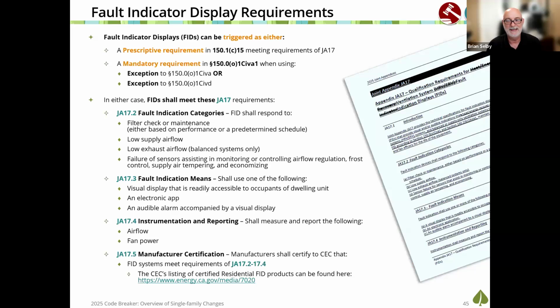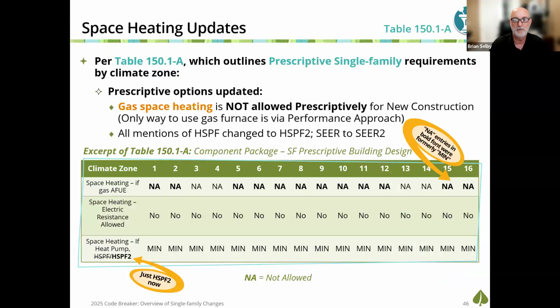There are some really in-depth requirements for this fault indicator display to qualify under the reference joint appendices chapter 17. Not going to get into these in any depth here, but just understand that minimum requirements have been set by the Energy Commission for these devices to ensure that they're indicating the correct issues, like checking the filter to make sure that it's clean, and making sure that air is flowing through it. So we want to make sure that those devices are functioning correctly and get maintained appropriately.